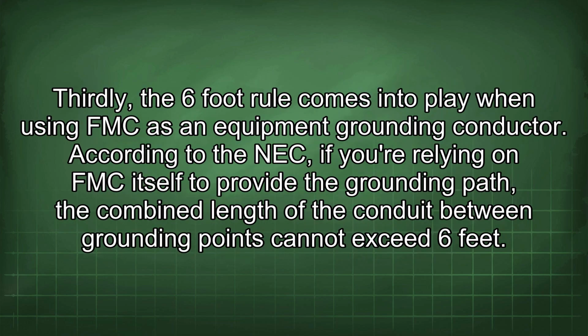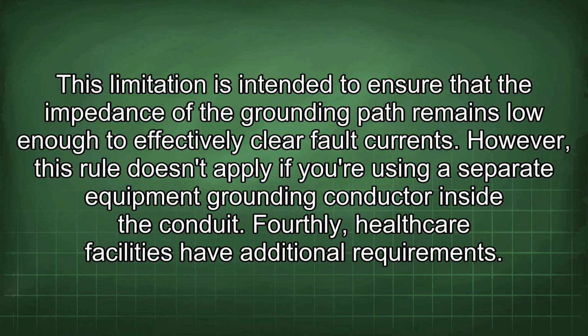Thirdly, the 6-foot rule comes into play when using FMC as an equipment grounding conductor. According to the NEC, if you're relying on FMC itself to provide the grounding path, the combined length of the conduit between grounding points cannot exceed 6 feet. This limitation is intended to ensure that the impedance of the grounding path remains low enough to effectively clear fault current. However, this rule doesn't apply if you are using a separate equipment grounding conductor inside the conduit.